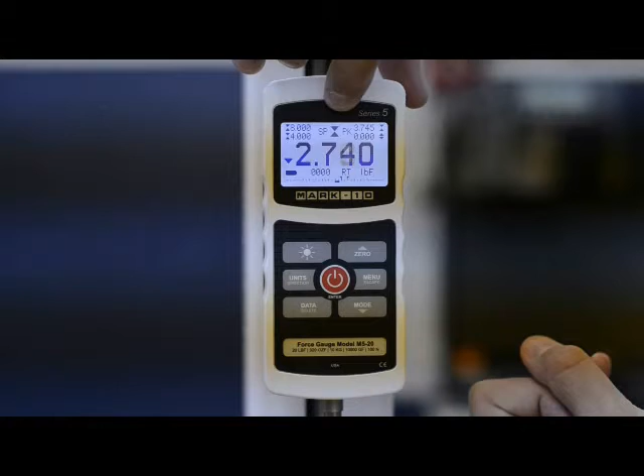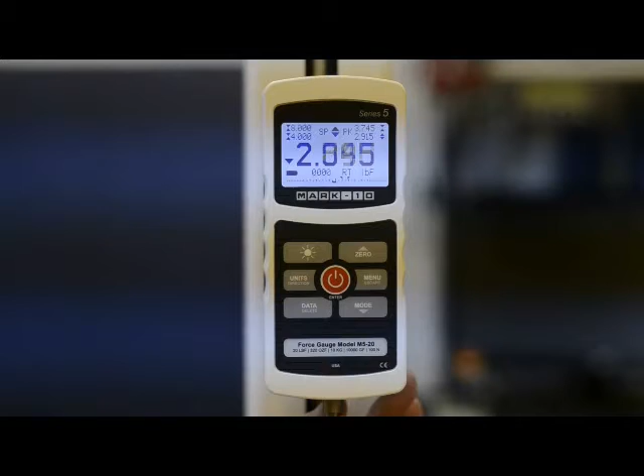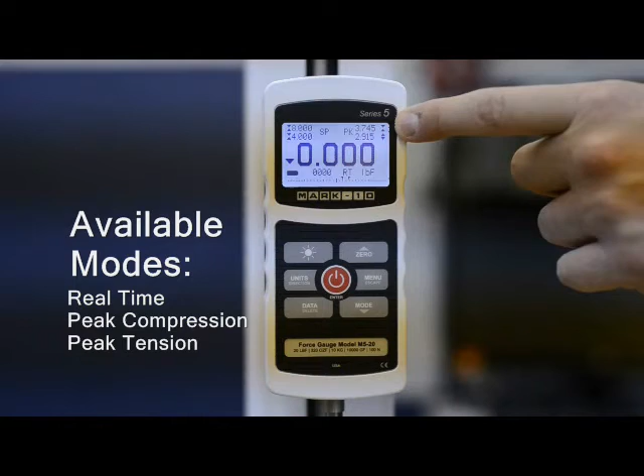This is your main home screen here where you see the current reading. Currently we're in real-time mode, which means it'll show you the live reading. I'm producing a compression force, so you'll see the compression symbol up on top. If I now pull on the shaft, it will show you the tension symbol, and it'll show you the tension force. The peak readings are always shown in the upper right corner there, your peak compression and tension readings.